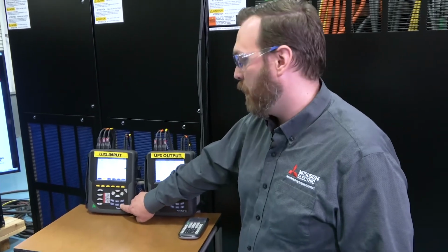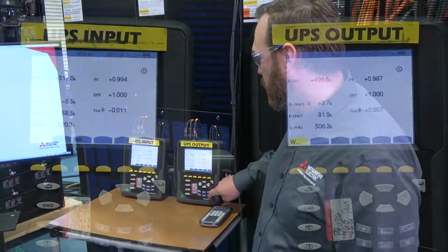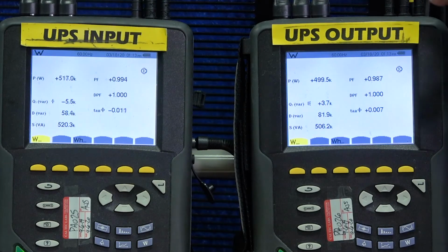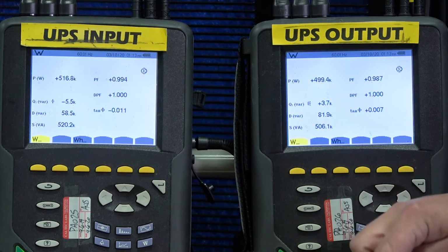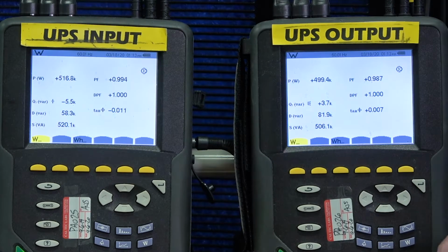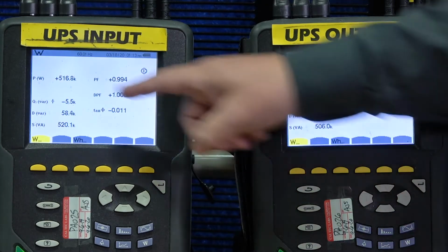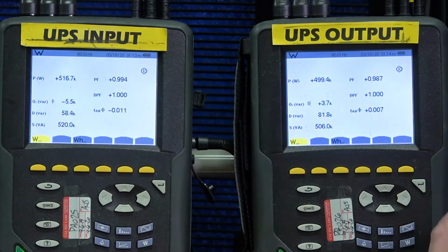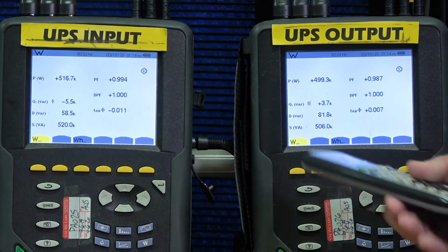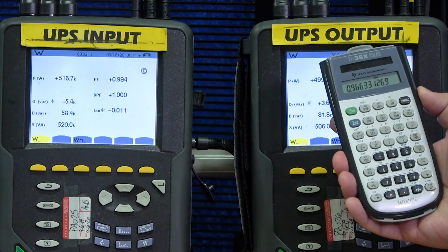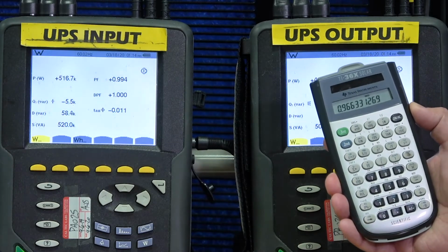Now let's take a look at our overall system efficiency. So now that the load banks have stabilized, we're at 499.5 kilowatts load. 499.4 kilowatts load divided by 516.8 kilowatt input load for a total overall system efficiency of 96.63%.